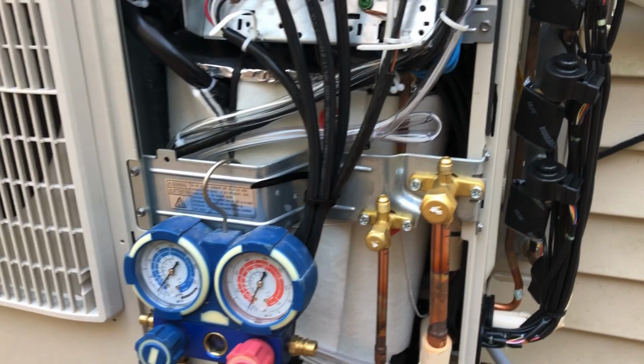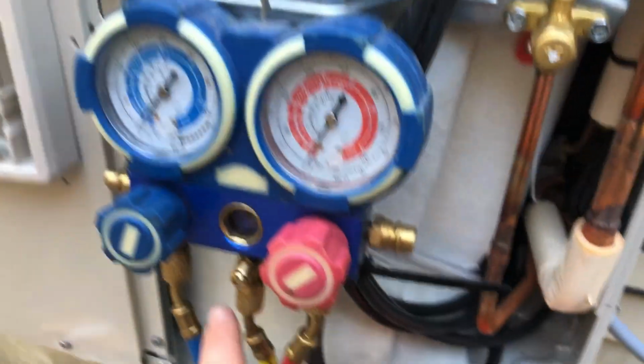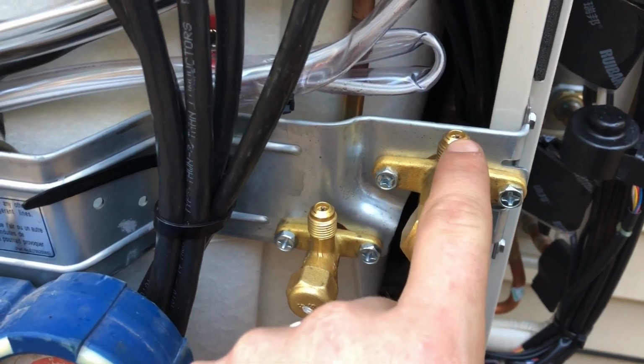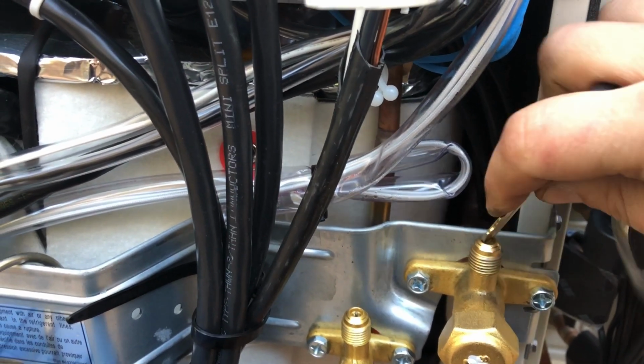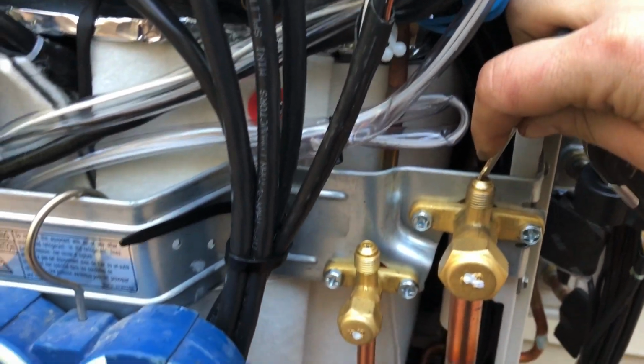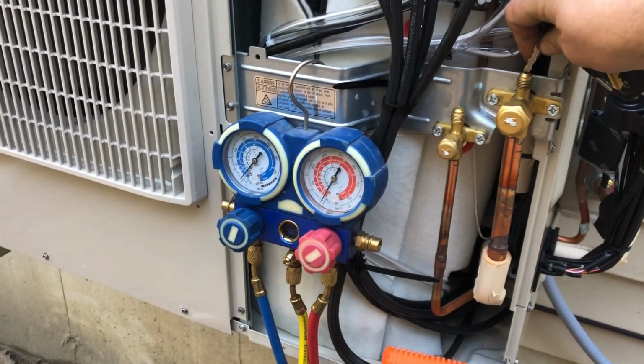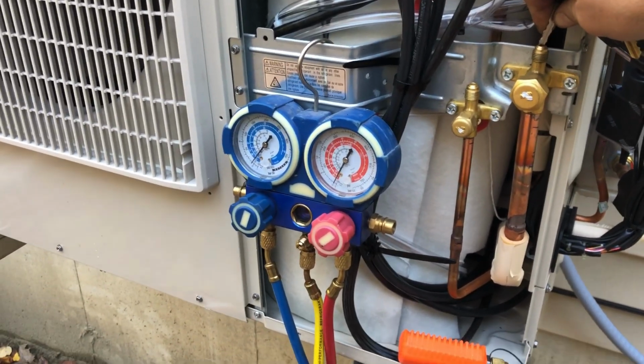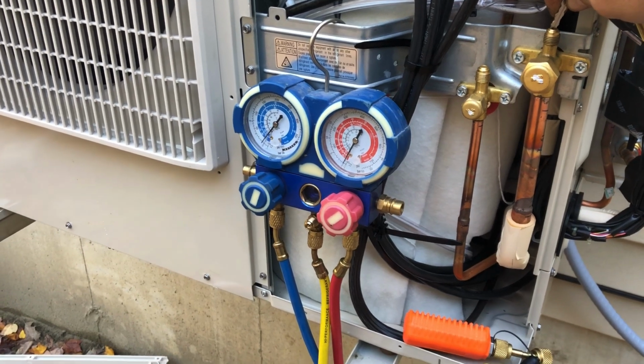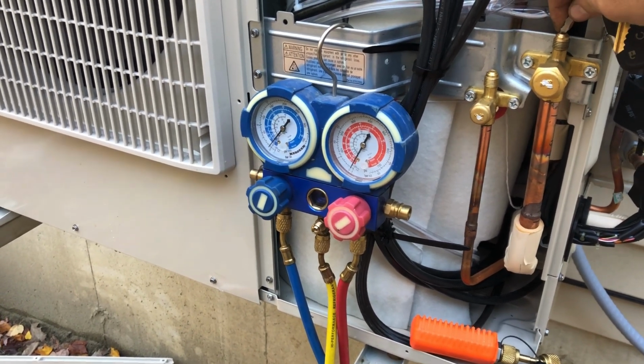Okay, I lied to you - by pushing this, you won't get the nitrogen out. You have to push both of these. You'll have to pop the hoses off and release all the air, or nitrogen - I keep calling it air - by pressing down on it. It should only take a few seconds, but you've got to get it all out of the system, because if not, your micron gauge will show a high pressure reading and you won't be able to draw vacuum.